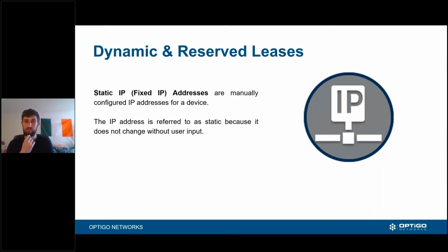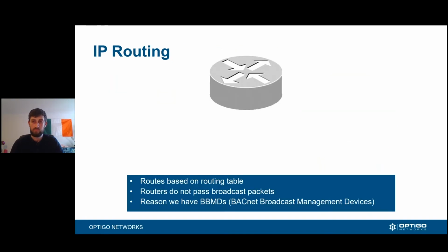Again, it's a little bit beyond an introductory session now, but we can help you there. If you are building a new system, try not to use static IP addresses, mostly because in the future, as you grow and your subnet runs out of space, it's all manual work. You have to go to every device and manually change the information, as opposed to using a DHCP server, where you can change it centrally and everything gets affected from there.